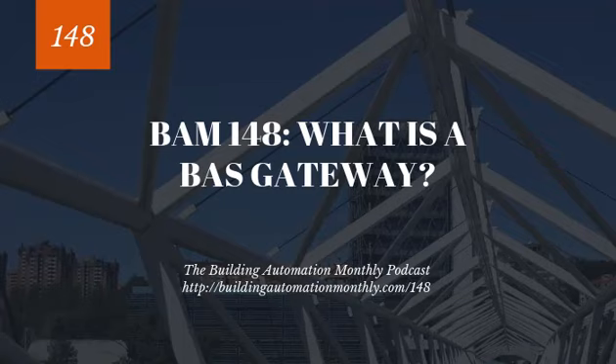Now, physical gateways simply exist to convert physical media. Let's say you've got a building, it's MSTP, and you want to transfer to another building, but that's too long for your MSTP run, so you may do RS-485 to fiber to RS-485. Signaling will then allow you to transfer your data between buildings.